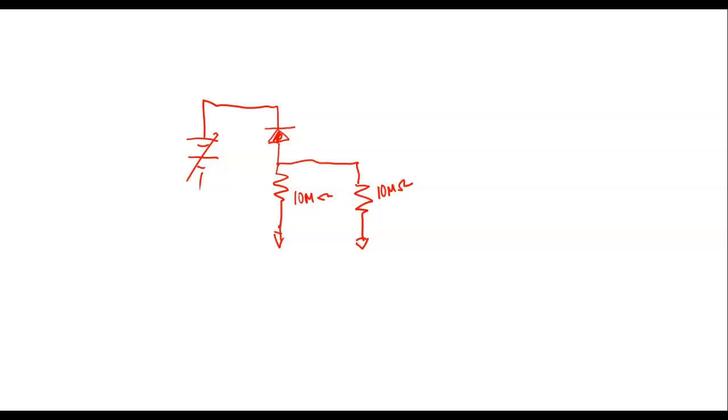We had a guy working at US Steel, and he wanted to measure the voltage out of a mag amp. This is what we used to do before we had operational amplifiers and everything. And it has an extremely high impedance. And he went over there and he put his voltmeter across it and shut down the line just like that. Because he didn't take into consideration he would load that mag amp down. He would change the voltage out. All the electronics said, hey, something's going on. The speed's not right. And it shut the whole line down in a heartbeat.